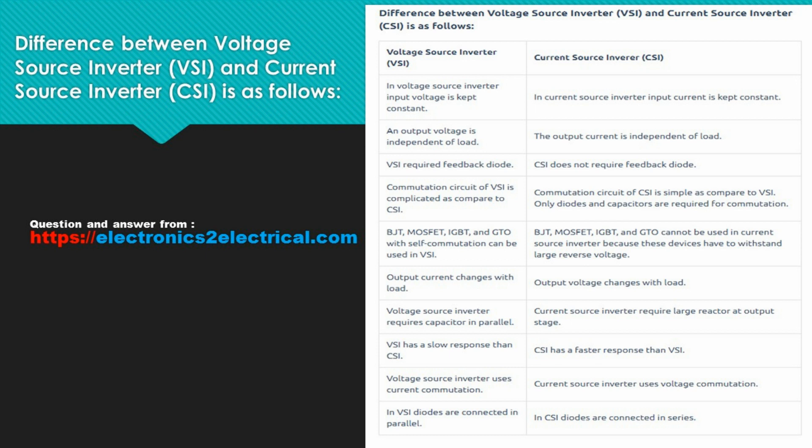Output current changes with load in VSI; output voltage changes with load in CSI. Voltage source inverter requires a capacitor in parallel. Current source inverter requires a large reactor at the output stage. VSI has a slower response than CSI; CSI has a faster response than VSI. Voltage source inverter uses current commutation; current source inverter uses voltage commutation. In VSI, diodes are connected in parallel; in CSI, diodes are connected in series.